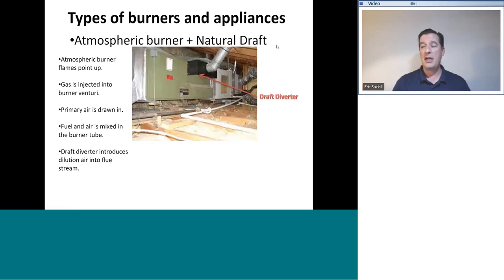Horizontal furnace of the same era, same brand. These are going to be found in an attic or in a crawl space. This is what I call a dedicated horizontal furnace. And if you are in an attic or a dark and dank crawl space, and you do not see the draft diverter immediately in front of you, be aware that the original installer had a choice of where to put it and a choice of where to put the gas valve. The draft diverter and the gas valve aren't always on the same side of the appliance. So in this example, you would be working on the other side of the appliance where the gas valve is and the burners are.